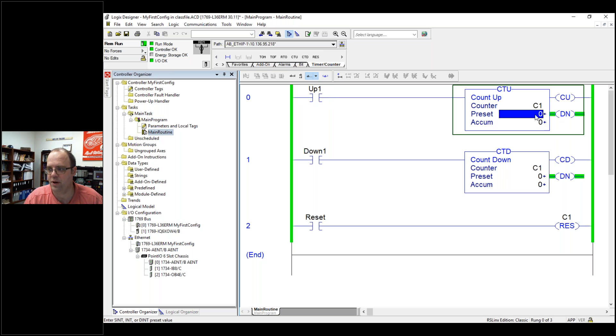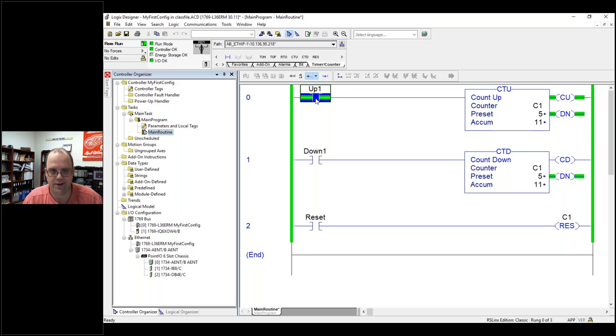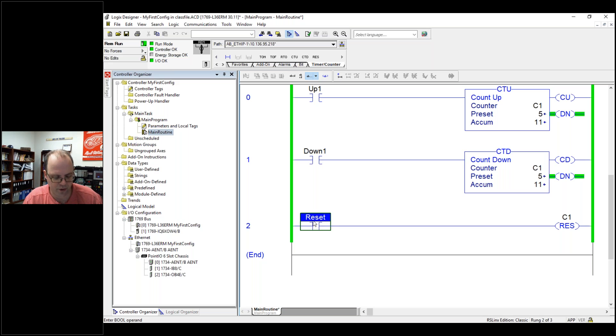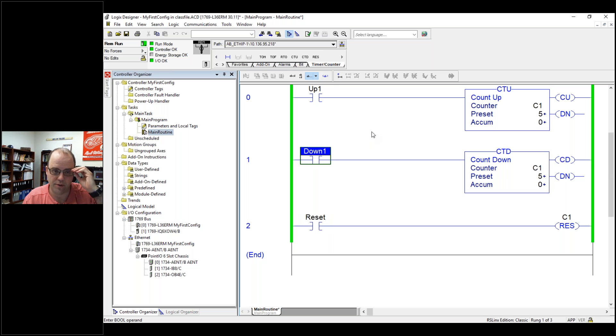I'm going to untoggle this. Once I put a preset value in, notice what happens to the done bit — I'll put it in at five. The done bit turns off. Now if I toggle up, and now it's done — I can keep going. Say I want to subtract one — maybe it's a parts counter, everything's fine. But say if I'm at the end of the day, this is when I hit my reset. With the reset on, you'll notice the accumulated value is not going up — it's staying the same because the reset bit is true.